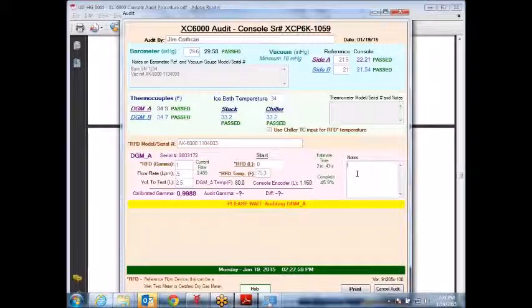So far, this is pretty much making sense, the flow of it and all. Yes. So right now this is left on A side. So that's the one we checked last, whatever you used last. You just start with that. Where you put your vacuum check. Yeah. Where you check A and B side. Correct. There's no particular order we have to do it in. Yeah, you got to do A first. So that's another one of the gotchas. You forget and leave it left on B. All right. And that's why it pops up and tells you connect to the A inlet. Yeah.